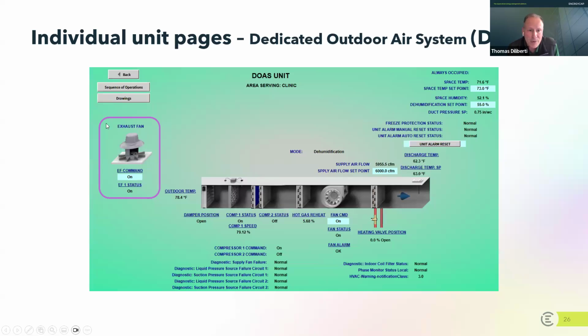And the other thing, and why I put this in the purple box here, is these systems always have to be tied back to an exhaust fan. Because if you're bringing in a bunch of air into a space, you can overpressurize the space if you don't have a fan to remove air from the space. And so you want to make sure that this is programmed correctly and that when you're looking at building pressure or these set points, everything seems to make sense. And again, just highlighting the most important thing, these DOAS units have to be connected to an exhaust fan. So we need to make sure the programming is right in order to keep the building pressure right.